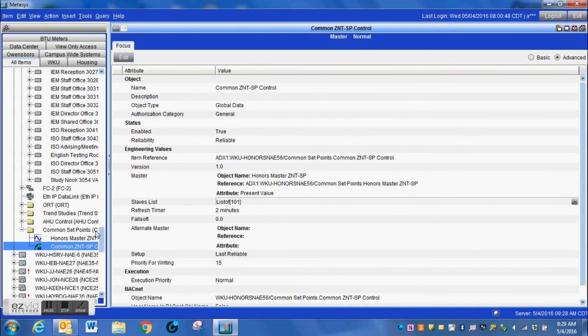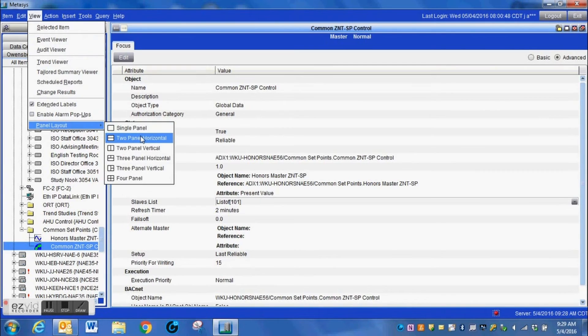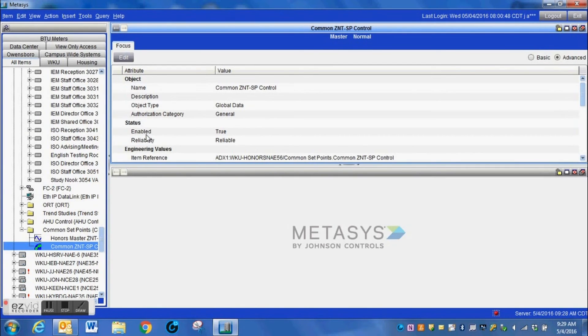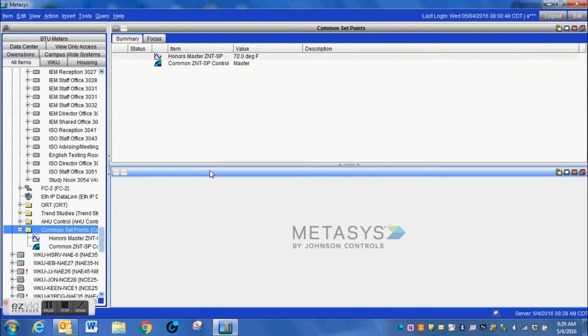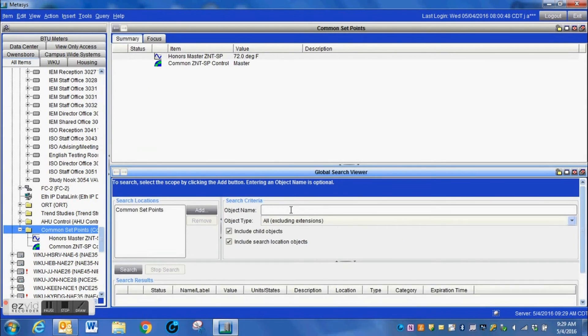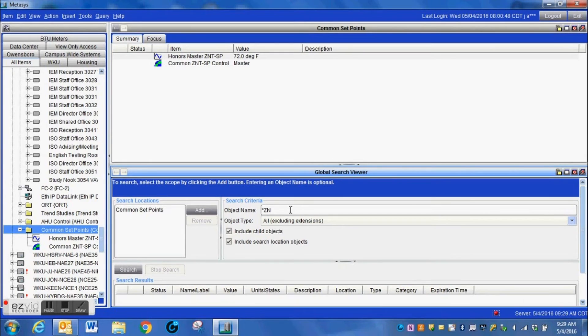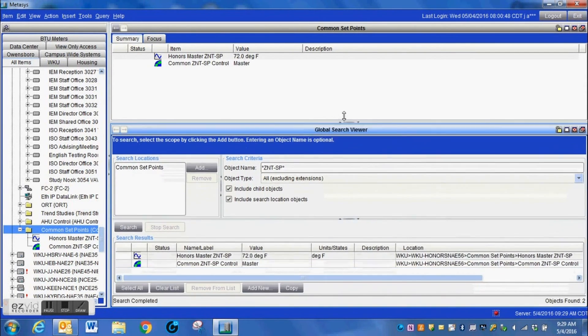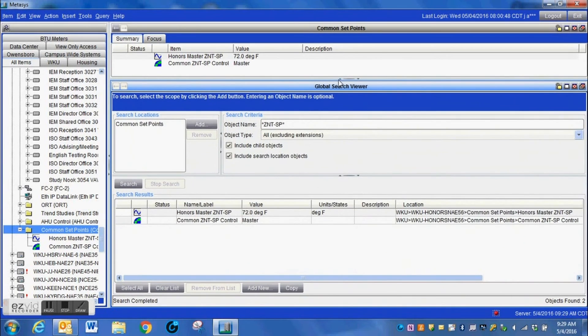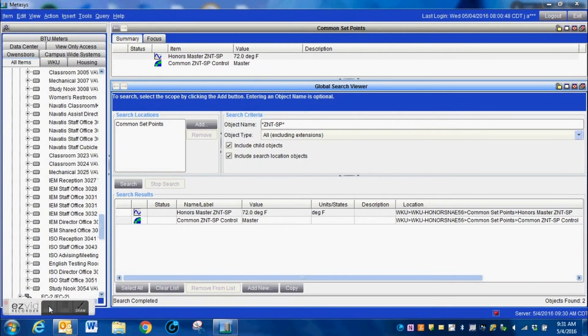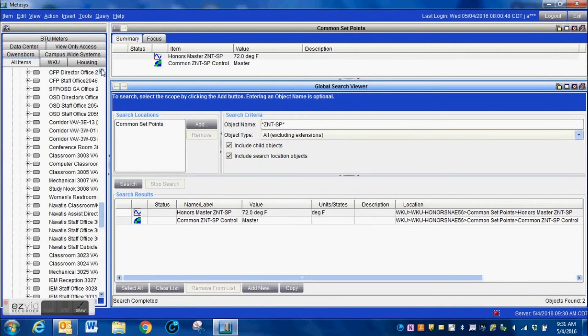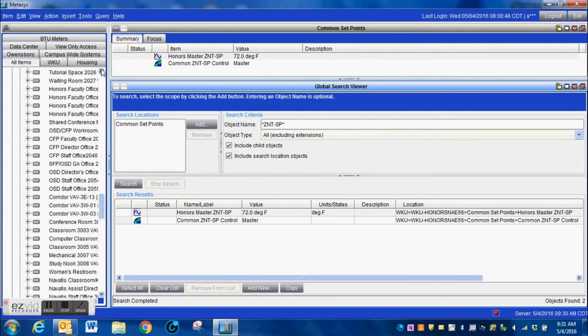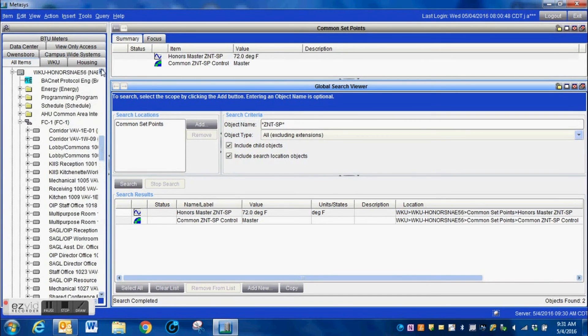Now that we have the majority of our building added to this, what we're going to do is actually demonstrate what it does. I'm going to open up here a window to where I can do a global search for all the common zone set points to where you can see all of them change at once. But you need to know that within the configuration of the global data share, you can do a refresh time of however many minutes. It comes set up as a default, that it will rebroadcast its value at two minutes. That is something that you can change. You can change it to five minutes, 15 minutes, whatever. You don't necessarily need that changing every two minutes in your system. It's not something that you really needed to do that very often.